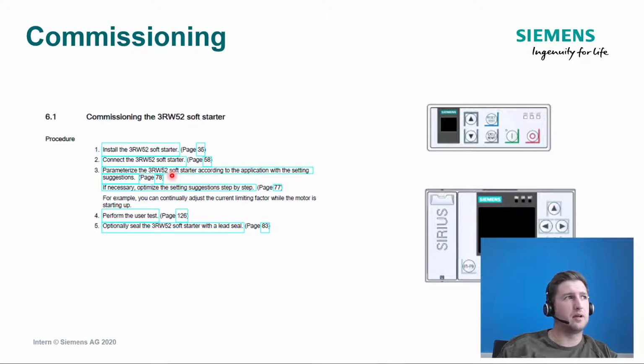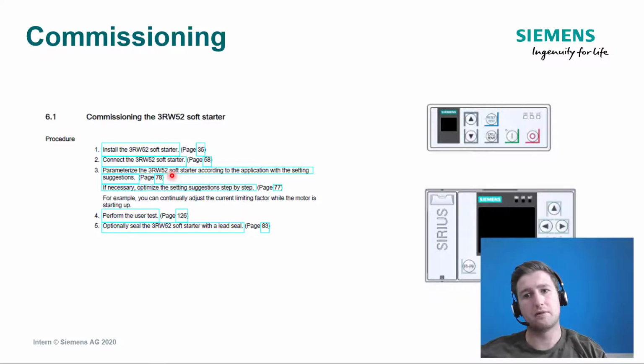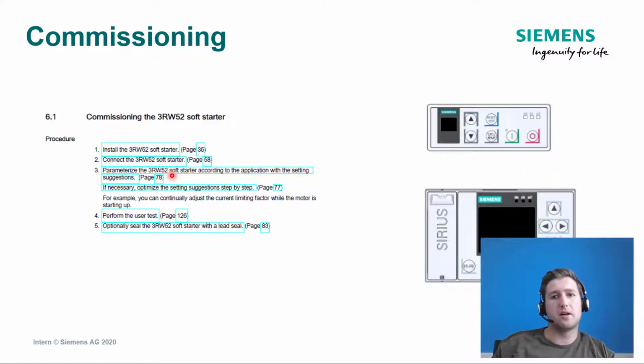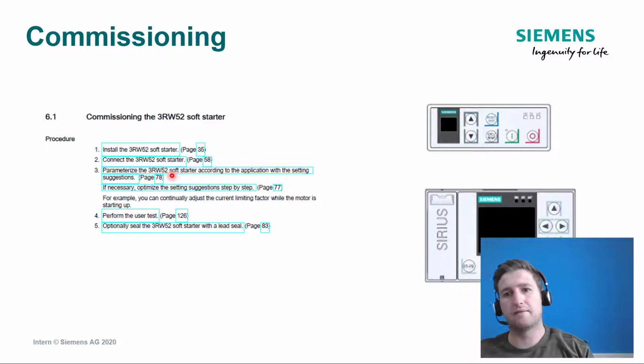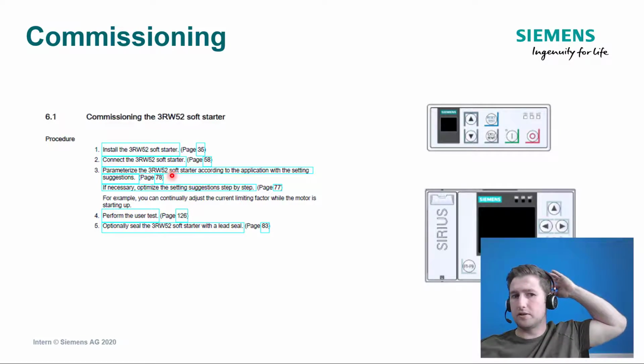What starting voltage do we want the soft starter to ramp up from? Say for example, if we had a circuit which was at 400 volts and we initiated a start at 50% of the starting voltage, it would start the motor at 200 volts, and then dependent on the ramp up time that we set, it would take that time to ramp up to the full load voltage of 400 volts. So it would increment from 200 volts. Say if we set a ramp up time of 10 seconds, it would take roughly 10 seconds to reach from 200 volts up to the full line voltage of 400 volts.